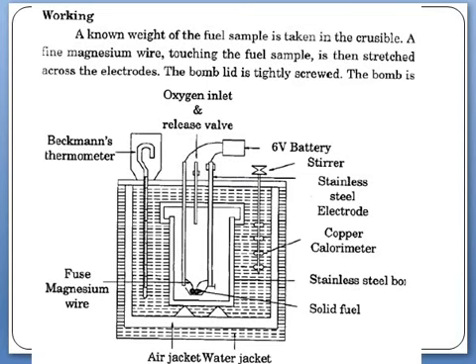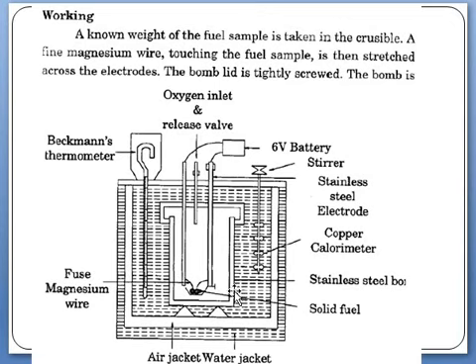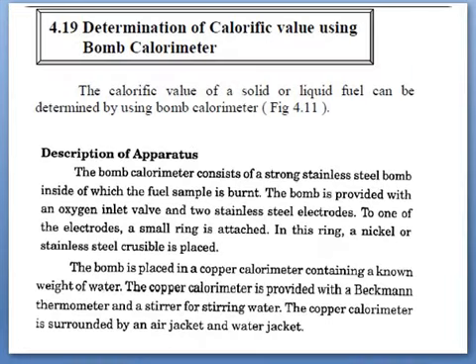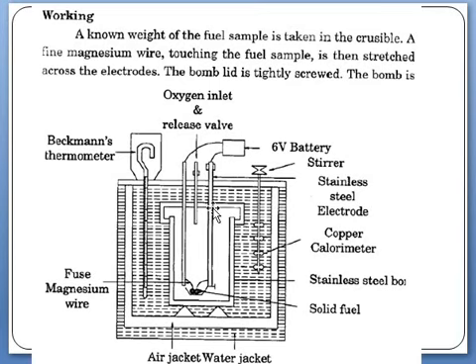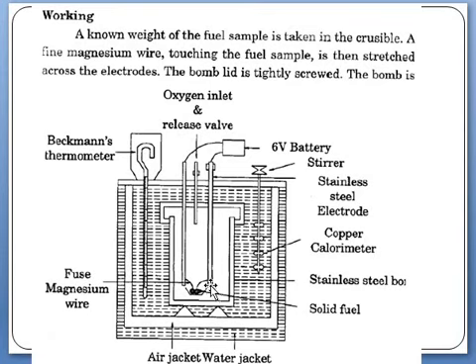The bomb calorimeter consists of a strong stainless steel bomb inside which the fuel sample is burnt. The bomb is provided with an oxygen inlet valve and two stainless steel electrodes. Current is passed through these electrodes, and the magnesium wire in contact with the fuel causes ignition. To one of the electrodes, a small ring is attached, and a nickel or stainless steel crucible is placed on this attachment.